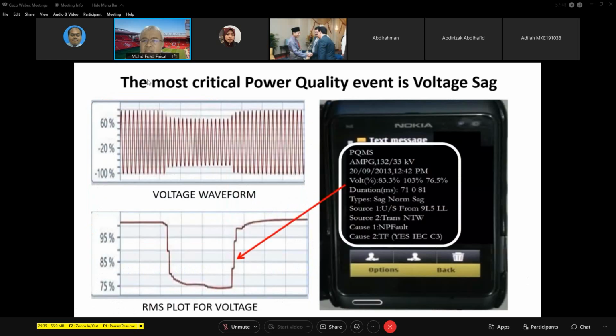But okay, the most critical power quality disturbance is voltage sag. As you can see in my slide, the voltage is reduced slightly and returns to normal. And I'm now comparing the sine wave and the RMS value. You can also see the SMS. This SMS is from the TNB system. It will send an SMS every time there is a power quality event. In this case, there was a voltage sag event in Ampang. So the system is very sensitive. It will detect, classify, and diagnose the event. So PQ is the most important or critical event to customers.